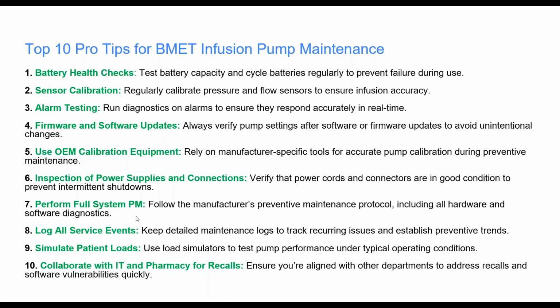Test your alarms, make sure they actually alarm. Fortunately, in the case I brought up to you, we had tested the alarms, and that had been proven to work, at least during the time we did the preventative maintenance. But as I mentioned, we still retested the alarms to make sure those alarm conditions would have been annunciated.